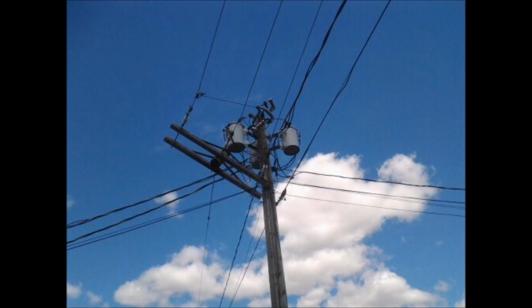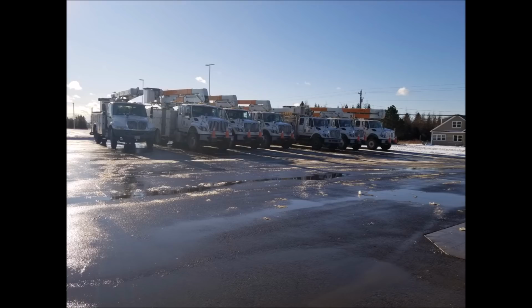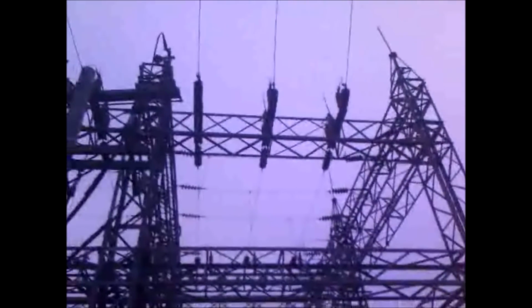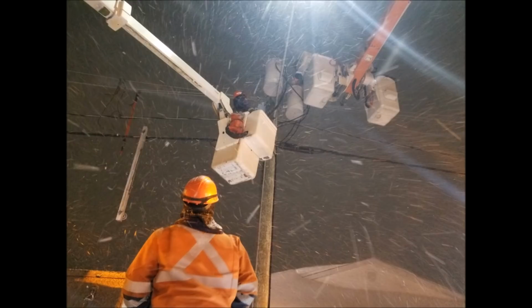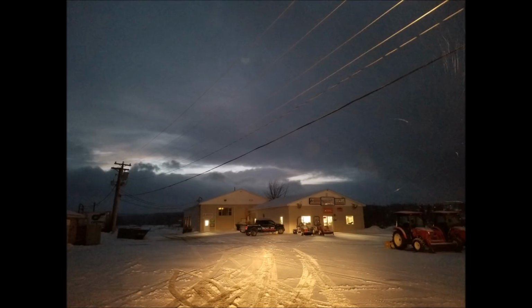In cases of these large-scale outages, relays and various alarms will notify the proper authorities, and I can assure you, response is quick. Behind the scenes, several people have already begun the troubleshooting process, as well as crews that are quickly being dispatched. It's safe to say that if the outage affects the lines all the way back to the substation, chances are we are aware. Even if it's a smaller sub that's not equipped with all the fancy relays and alarms, local businesses and homes where electricity may be more of a priority are pretty quick to call.